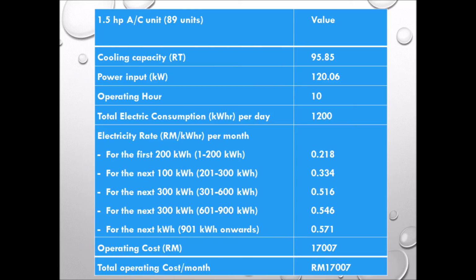So for the 1.5 horsepower air conditioning unit, we got the total electric consumption per day at around 1,200 kilowatt hour for 89 units of air conditioner. For the total operating cost per month of this air conditioner, we got around 17,007 ringgit based on the tariff from the TNB.